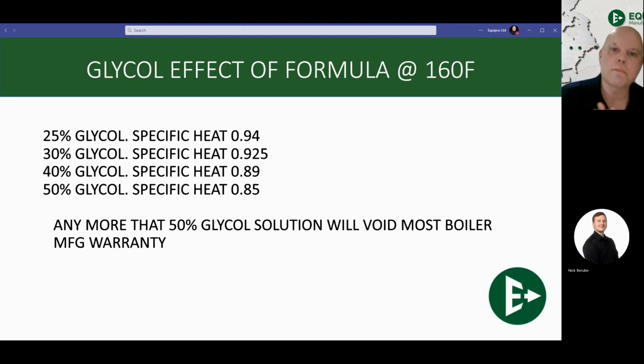Let's talk about this. If you are talking about a glycol with a 25% solution, you're no longer multiplying that number by 1. You are multiplying that number by 0.94. So it's 8.33 times 60 times 0.94. That'll give you the BTU output at 25% glycol solution. Now looking on the chart here, let's pick on 2 of these numbers. Let's pick on 40% glycol and 50% glycol. As you see, we're no longer multiplying by 1. We no longer have 100% heat output. Glycol decreases the heat efficacy of the fluid medium transferring that heat. So at 40% glycol, you have a specific heat now of 0.89, meaning that we've lost 11% of the heat efficacy of that water solution.